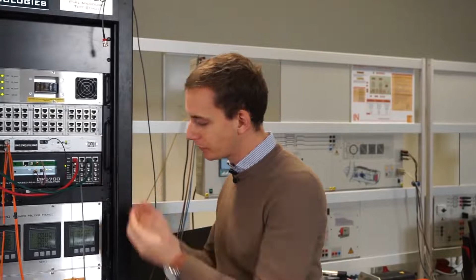This set point can be sent from the CPU, but you will be limited by the CPU time step. So if you have a power system model running at 50 microseconds, only one point every 50 microseconds can be sent from the simulator to the amplifier. For high frequencies, higher than 1 or 2 kilohertz, we highly advise using the FPGA generation to send set points. You will benefit from a higher resolution thanks to the FPGA clock.